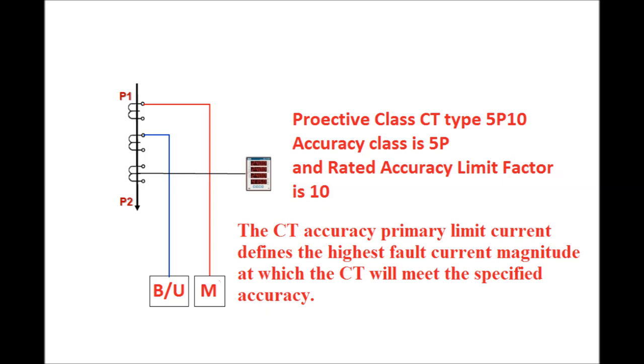The rated burden of the secondary side is defined on the nameplate of the CT. For example, if the rated burden is 20 VA and 20 VA is connected in the secondary side of the CT, then under rated current the burden will be 20 VA. Under this condition, the accuracy limit factor is 10 and the error is limited to 5%. So the accuracy limit factor also depends on the burden connected in the CT's secondary side.